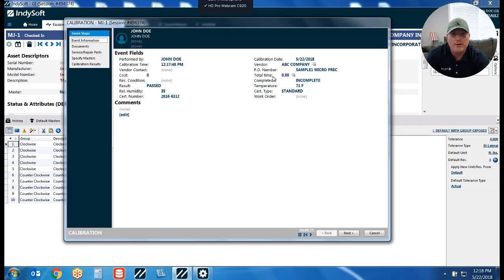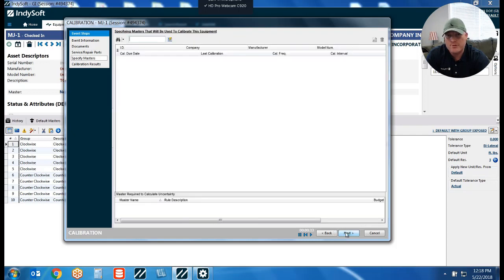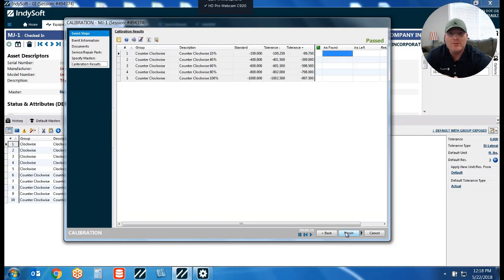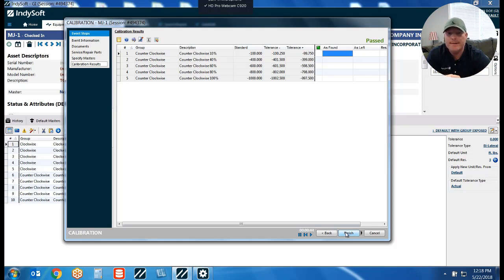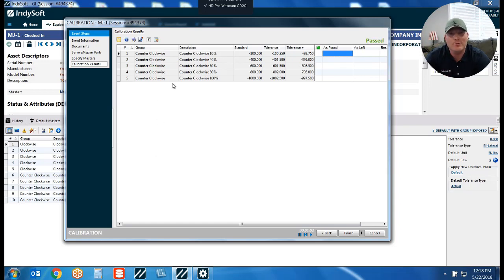When I hit OK, now we're in our standard calibration event. We've got our who, what, when, where step, our procedures, charges, repair parts, and of course your standards and masters if you're using those. But when we get to our calibration or test point window, you'll notice only the counterclockwise measurement points defaulted in. The reason for that is we created that option where you choose which set of test points you want to measure against. Behind the scenes all those test points exist for this item, but we chose only the counterclockwise points, so that's what defaulted in.